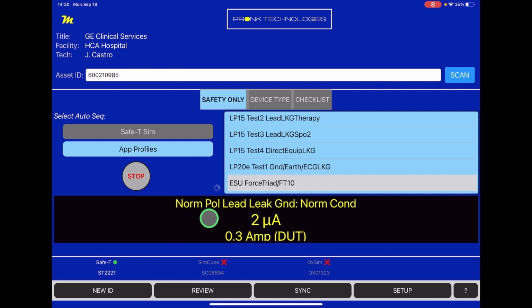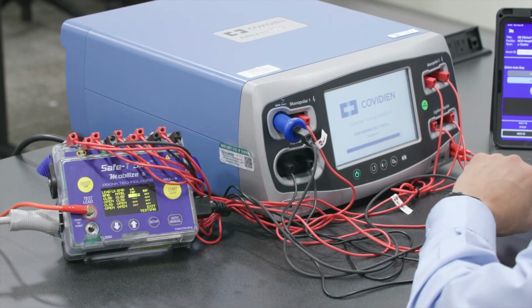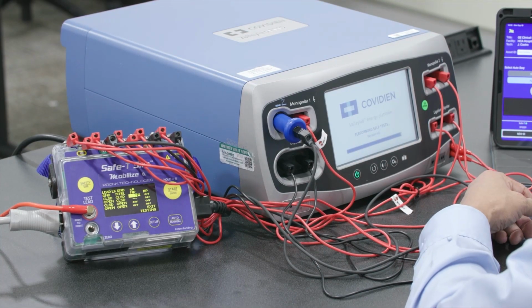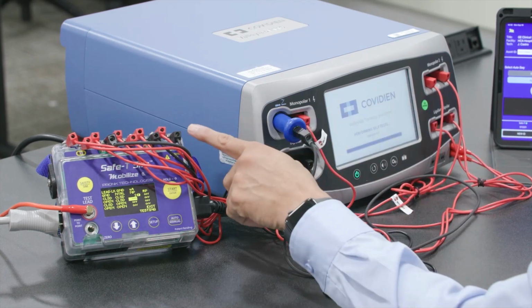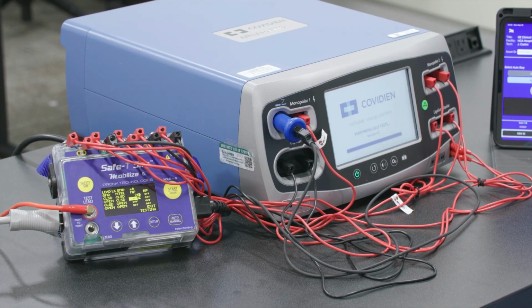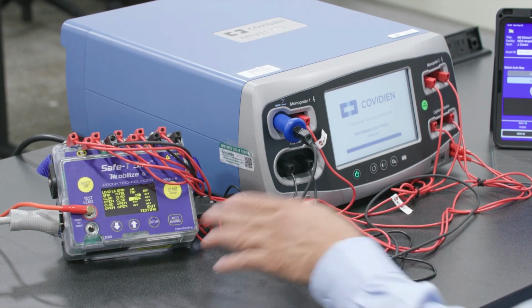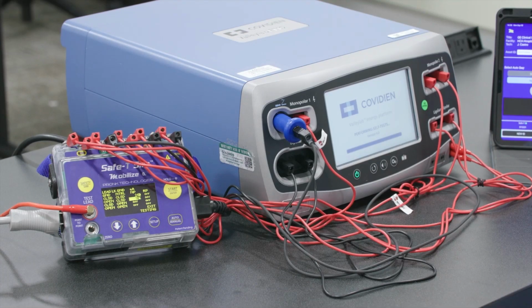It's important to realize too that part of this testing includes energizing the applied parts, as we say, to mains, unapplied parts, as I mentioned earlier. This is where these leads will get energized to 120 volts AC. So you want to make sure you're not touching those snaps during those tests because it is applying mains voltage. It is current limited with a 120 k ohm resistor inside of the unit, but nonetheless you'll want to avoid touching them and having a problem with that.